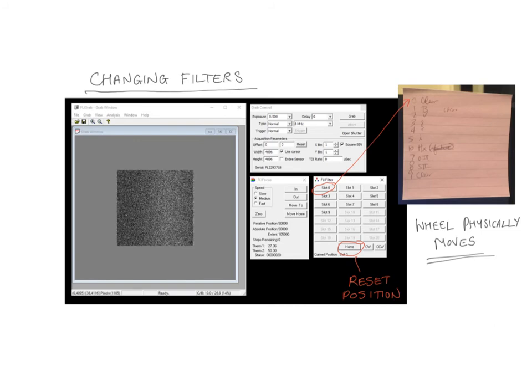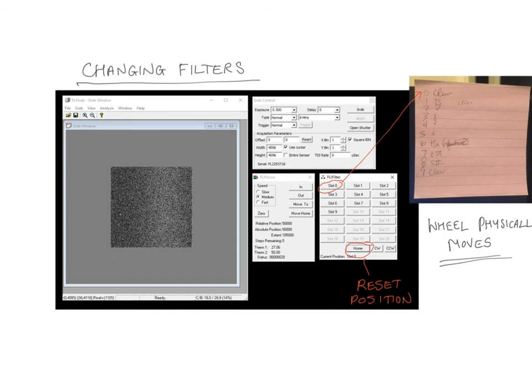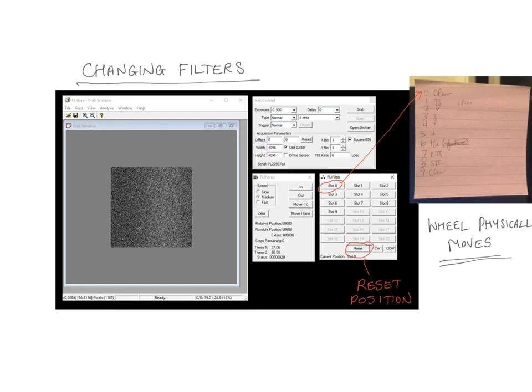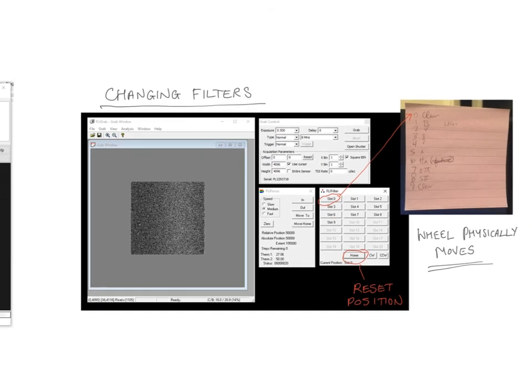You may want to take images through different filters. To do that, we use the FLI filter software. This labels things as different slots. There's a filter wheel, a physical wheel that has these different filters in them. We've put on the control room computer a little guide to which filter is in which slot. It doesn't always know where it's pointing initially, the filter wheel, so you may need to reset it before you start. Just bear in mind, this is a physical wheel that is moving. It's not like a computer game, it can take a little bit of time to move. Give it a bit of time.